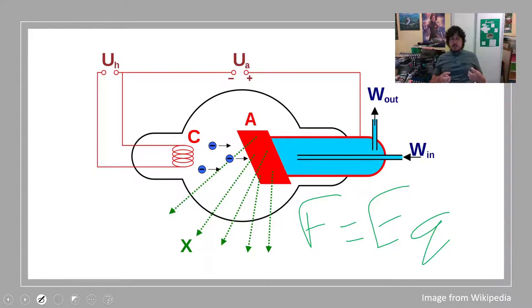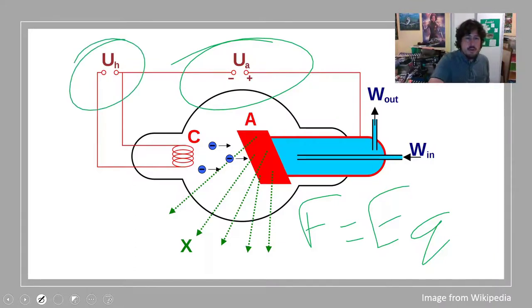If it's accelerating, it's gaining kinetic energy. Those electrons gain a mountain of kinetic energy and then smash into the target there. Most of it turns into heat, hence why you need water in, water out, and all x-ray tubes require some form of heat reduction. You'll note that there's a potential difference applied across the tube, generally in tens of thousands of volts, and also a potential difference across the cathode, which allows a current to flow too, which then boils off the electrons themselves.